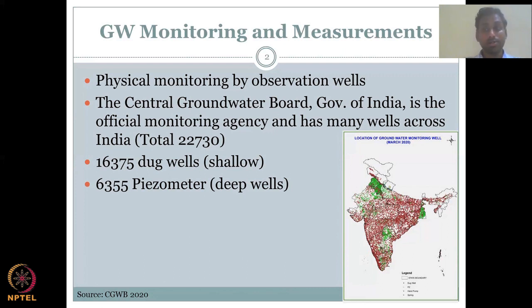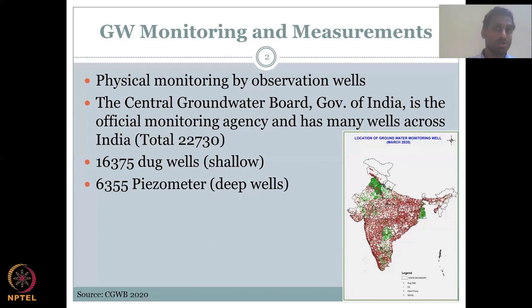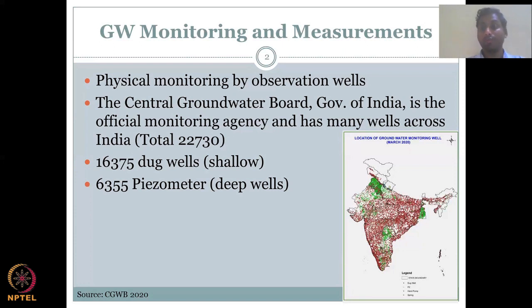The dug wells are mostly shallow — approximately 30 meters — and you normally measure with a tape or an automatic measuring device. For piezometers, which are tubes going more than 30 meters deep, you need automatic monitoring devices. In some regions like Chennai, groundwater has fallen to 250–300 meters, so you cannot use a tape — you need an automatic monitoring device, and that setup is called a piezometer.